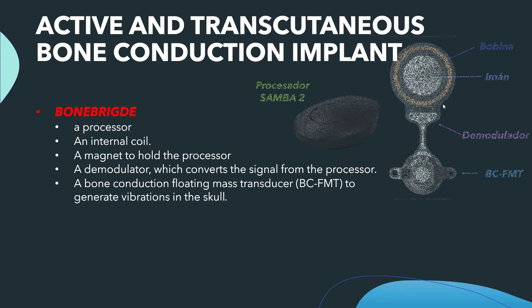For the transcutaneous one, we have the Bonebridge. So we will indicate it in conductive and mixed hearing loss that don't go above 45 decibels. For the CROS effect, the same as the Baha, the healthy ear must have at least 20 decibels threshold, and it's not indicated in kids under 5 years.